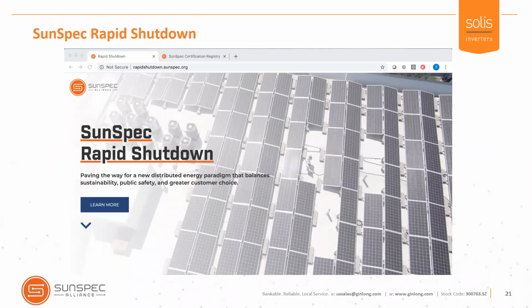Rapid shutdown is a very important standard. The reason is that NEC 2017 is now in effect in 34 states, and within the next two years the majority of other states will come on board. Already today there's a requirement for about 80% of the U.S. rooftop market to support this rapid shutdown standard, which is the ability to de-energize the conductors on the arrays so voltage can be reduced down to each individual panel level.